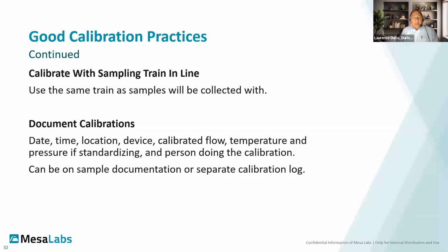Something that we see, and I differ a little bit with the calibrator manufacturers, I and the professional guidance say calibrate with the sampling train in line. Some of the manufacturers say keep the shortest possible length of tubing so that you have better consistency, but always sample with the sampling train in line so that you're calibrating with exactly the setup that you're going to be sampling with. Document your calibrations.